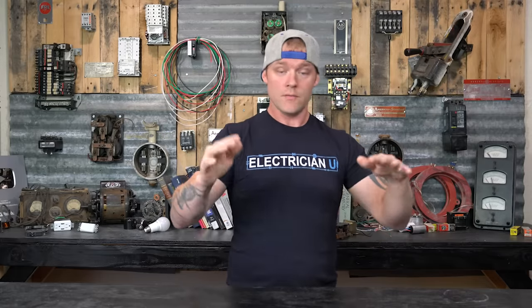Most of the time, utility surges are also a major concern. If there's capacitor switching or utility switches disconnecting and reconnecting, that can cause a massive spike of tens of thousands of volts — because you're talking about lines at like 7,200 volts — creating huge voltage drops or spikes across the entire system. So again, this is all about voltage. Don't be confused by joule ratings or amperage ratings — it's voltage, voltage, voltage. Although voltage changes do affect current since the two have a direct relationship.